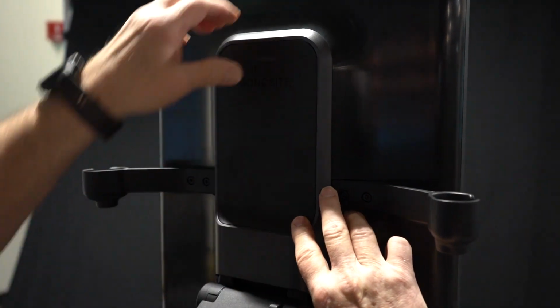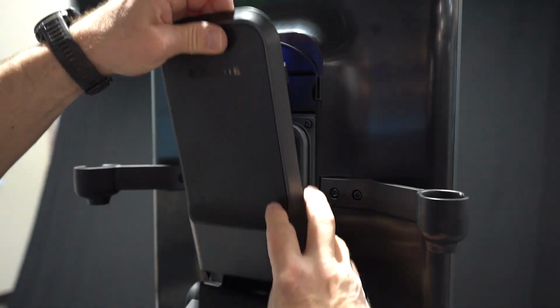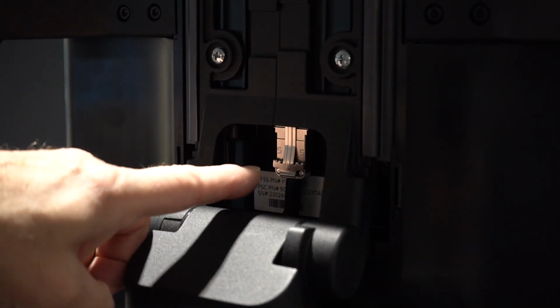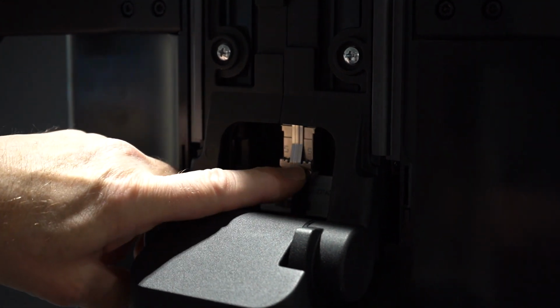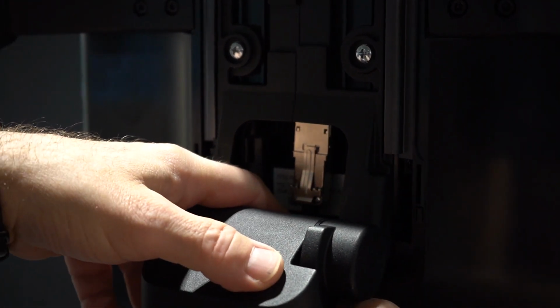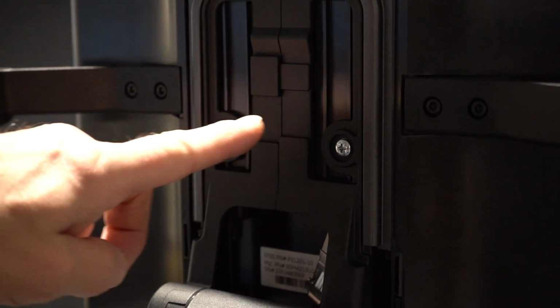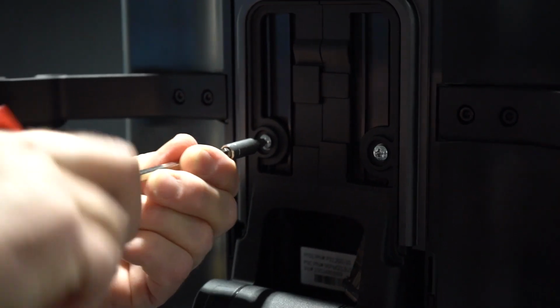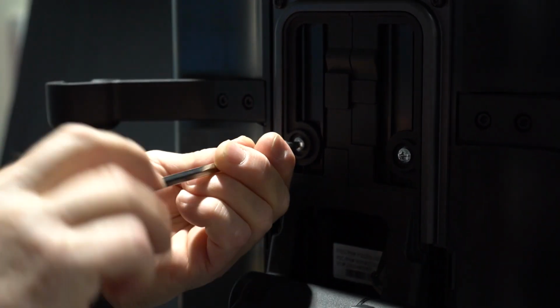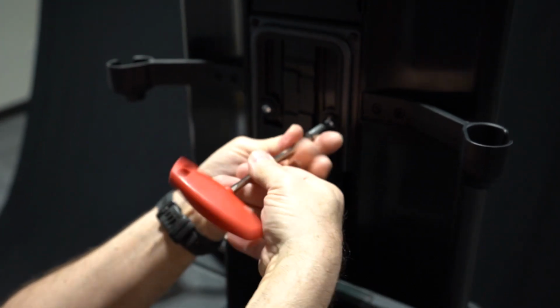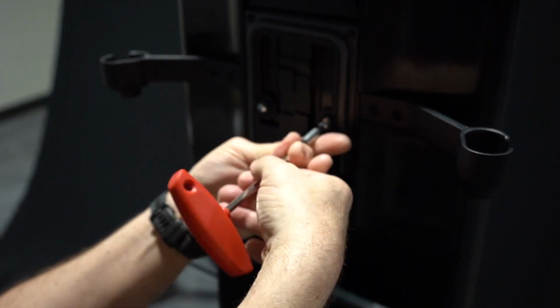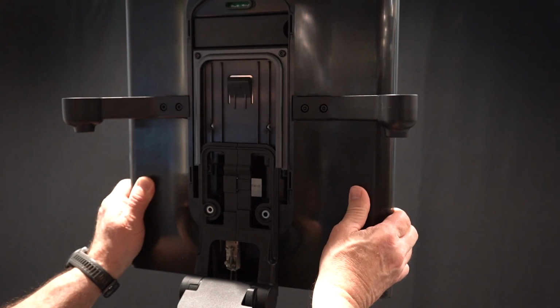Remove the clinical monitor cover by pushing up from the bottom of the cover to unlatch it. Disconnect the monitor video cable by pressing on the release and pulling the monitor video cable down. Use the magnetic bit driver and the number 2 Phillips head bit to remove the two M5 by 18mm screws securing the monitor. Lift the clinical monitor off the monitor mount blade.